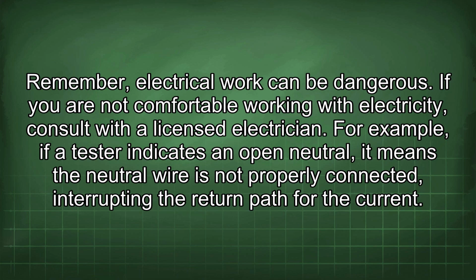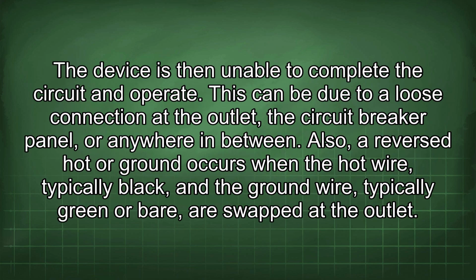For example, if a tester indicates an open neutral, it means the neutral wire is not properly connected, interrupting the return path for the current. The device is then unable to complete the circuit and operate. This can be due to a loose connection at the outlet, the circuit breaker panel, or anywhere in between.